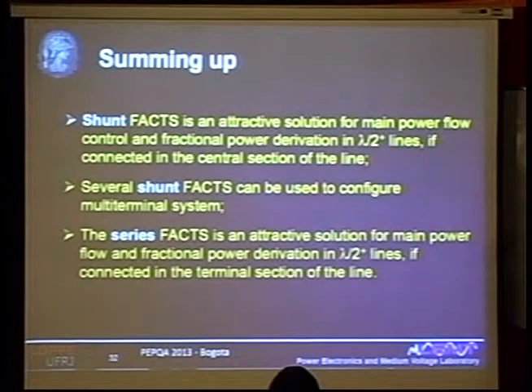Once again, just three items for you, since I have a lot of faith in this: this half wavelength plus line can be controlled in the same way as an HVDC system can provide. And more, with the advantage of not being literally point to point. There are some restrictions, but it's not point to point such as an HVDC system.